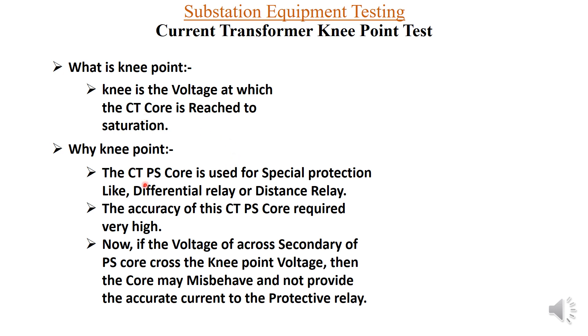The importance of the knee point is that the CT has a PS core used for special protection, such as differential relay or distance relay. If the voltage goes beyond the knee point voltage, the accuracy of this PS core will be compromised and accurate results will not be obtained. A very high accuracy is required for the PS core in the CT.